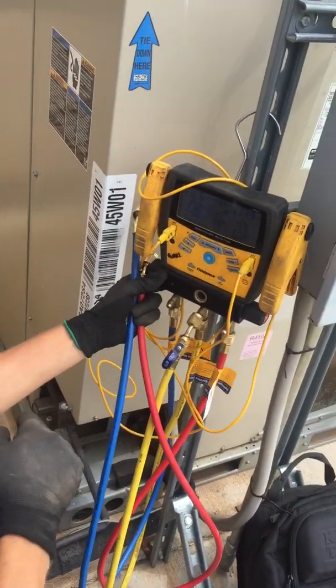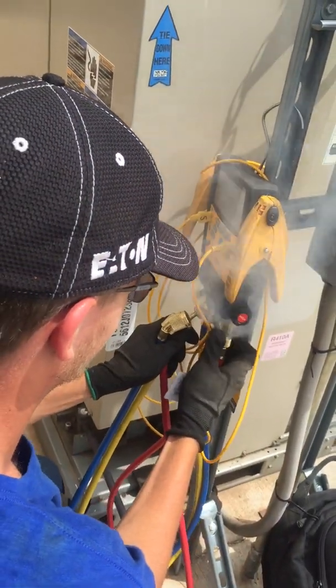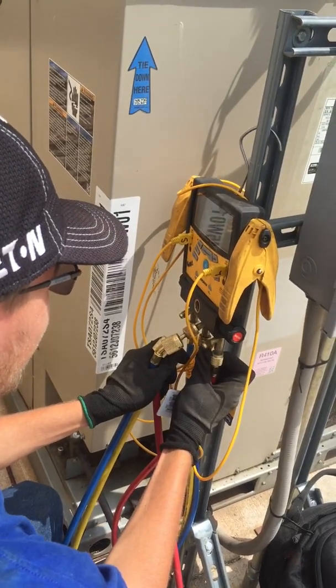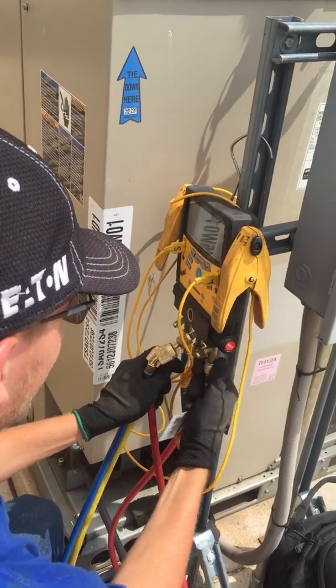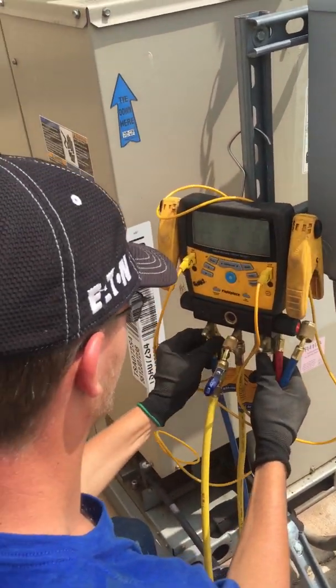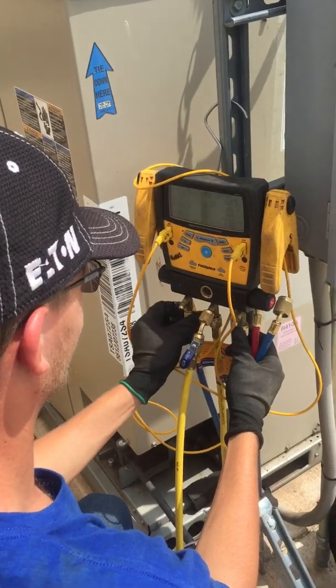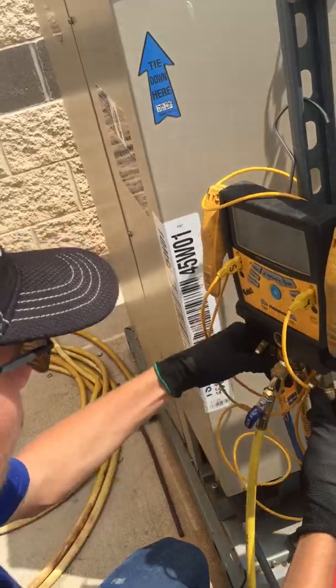Still got pressure here, so we're going to release that. Pop me off here and pop me off there, just enough to relieve the pressure. Now the same thing on your low side. And that's the 410 that was in there anyway — this is a 410 system, I'm not sweating it.